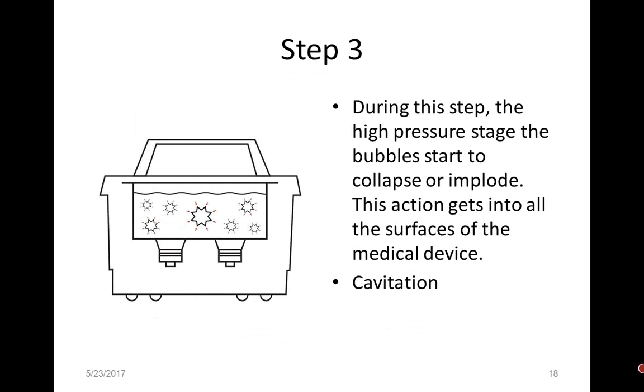During step 3, the high pressure stage, the bubbles begin to collapse inside and implode and go, boom, not explode, but implode. It's this action that gets into the surfaces of the medical devices. It is this cavitation. And these bubbles are created millions and millions of times throughout the solution. And they are imploding and creating small little vacuums in all the little nooks and crannies that you can't get with your brush or the lint-free wipes you're using. And it is pulling this bioburden, this debris, into the solution. And it's that implosion or that cavitation.